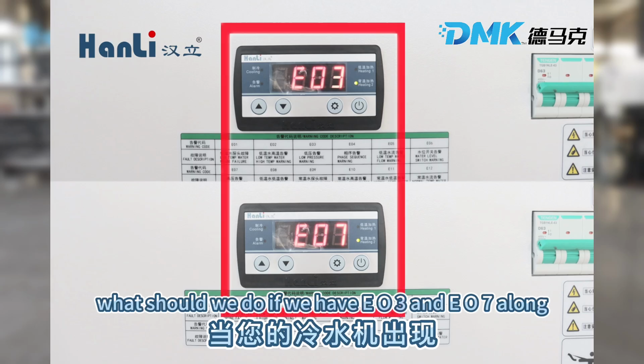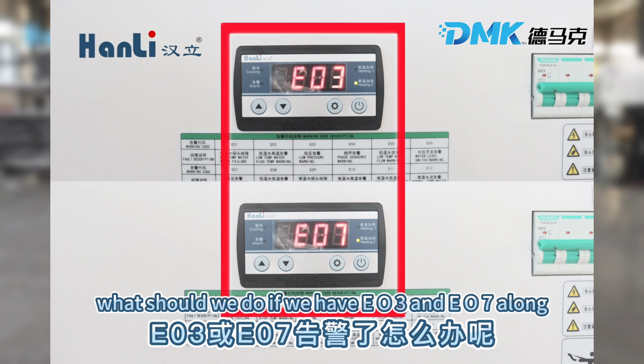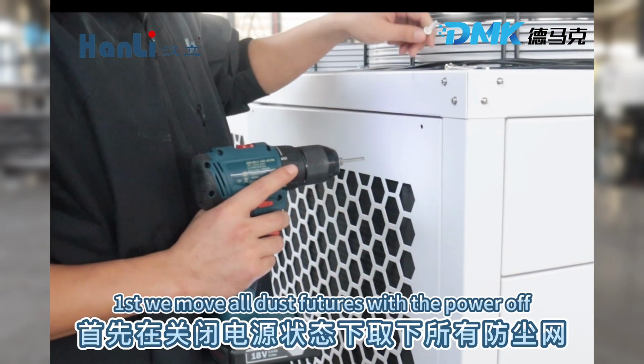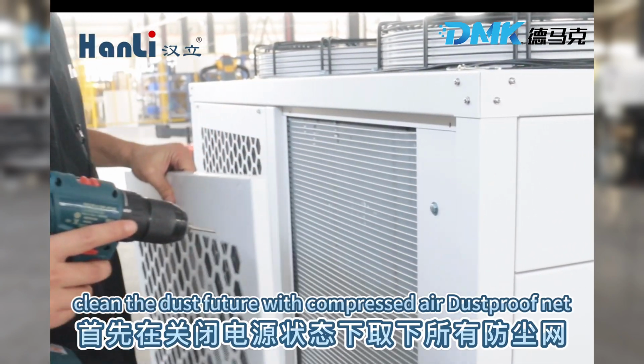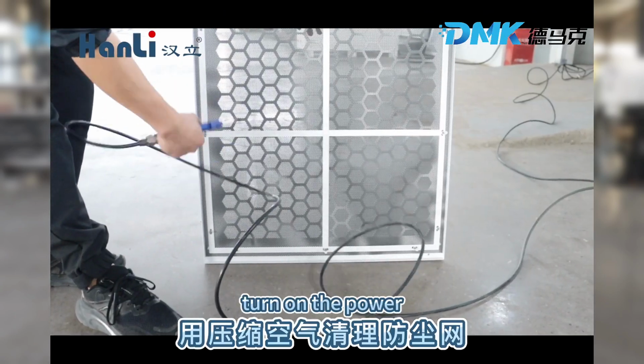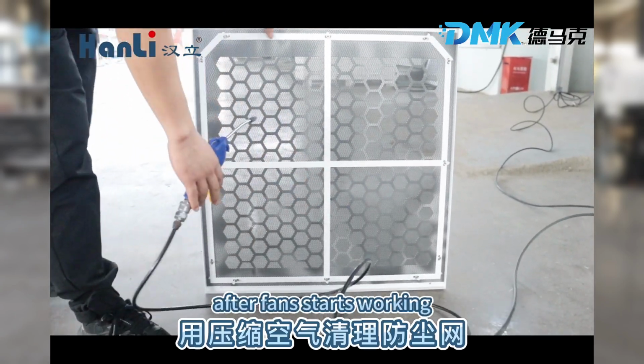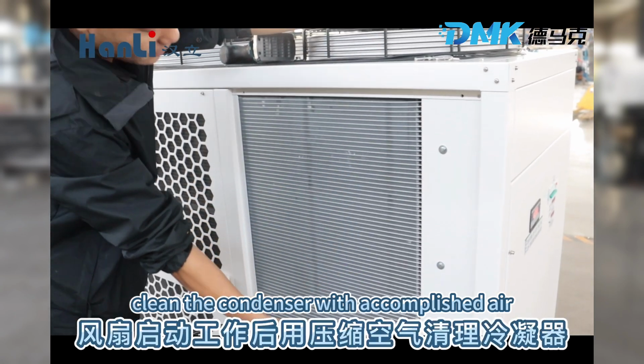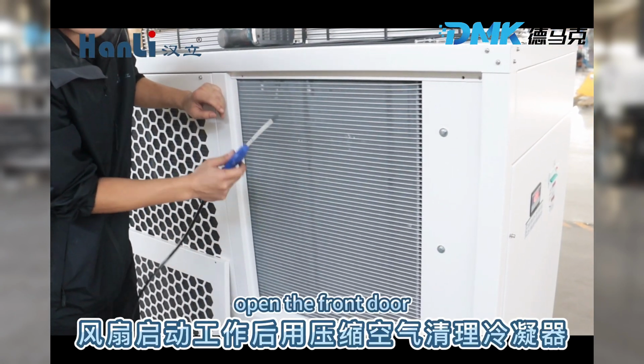What should we do if we have E03 and E07 alarm? First, remove all dust filters with the power off. Clean the dust filter with compressed air. Turn on the power. After the fan starts working, clean the condenser with compressed air. Turn off the power. Open the front door.